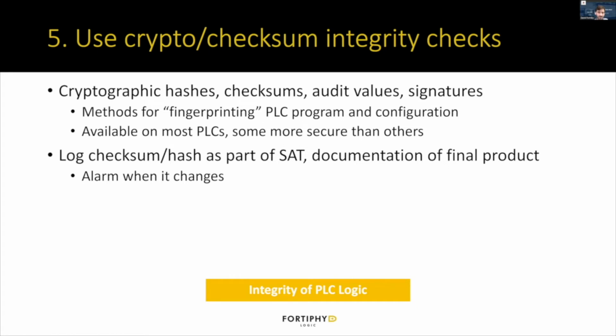The next practice is using cryptographic checks, or cryptographic hashes or checksums, as integrity checks for the PLC program. Different PLCs offer different things. They're all kind of given the same idea of methods for fingerprinting what the PLC program is and what the configuration is, and using that to quickly identify whether the PLC program has changed or not. There's a few different ways of doing this. PLCs range from using audit values or checksums or actual cryptographic signatures.